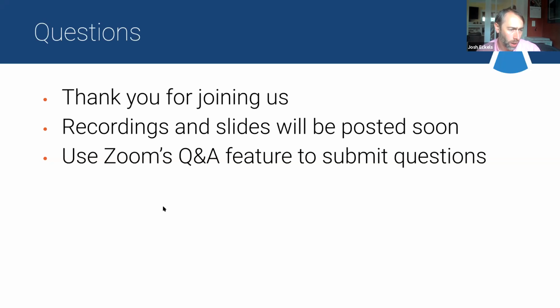I see a separate note on, is it possible to use AutoQC to stop the instrument when the system suitability moves out of bounds? Right now we haven't done that level of connection. There's the email notification like I talked about, and alternatively, our emails about recently imported data are immediate.